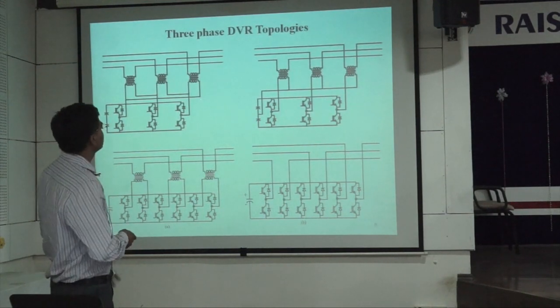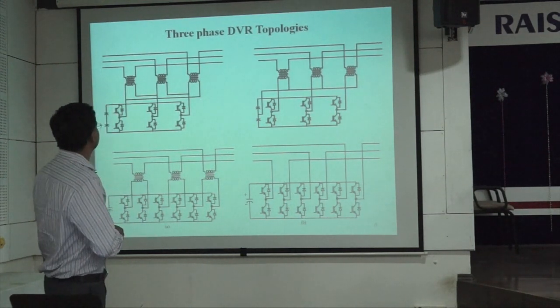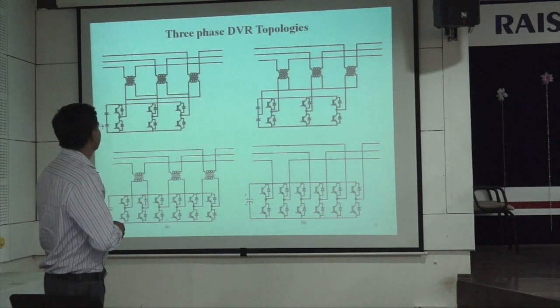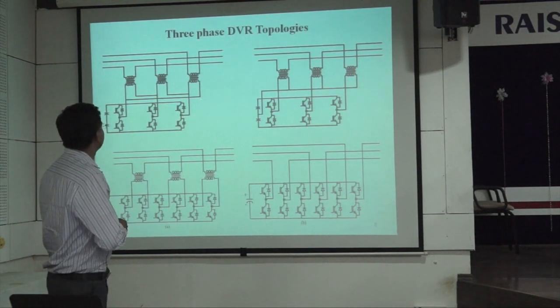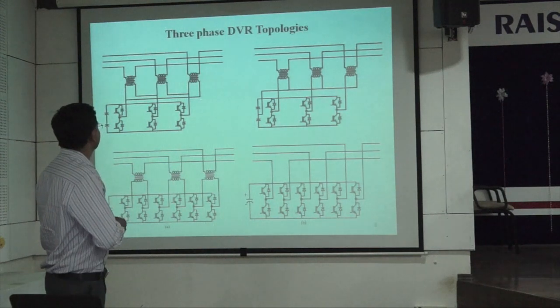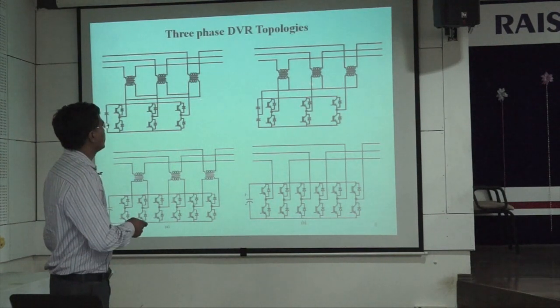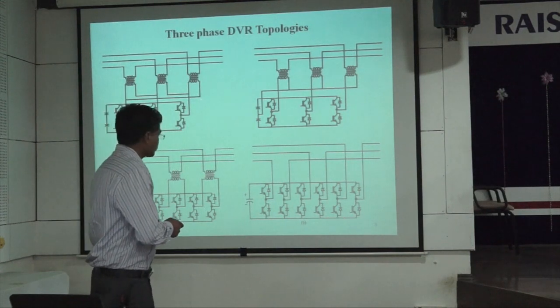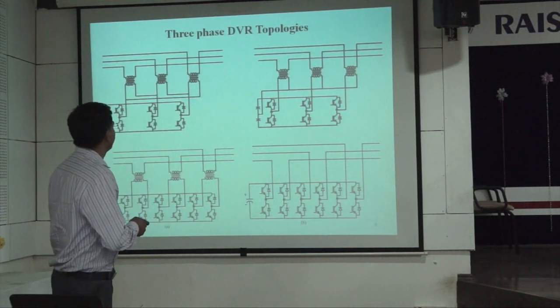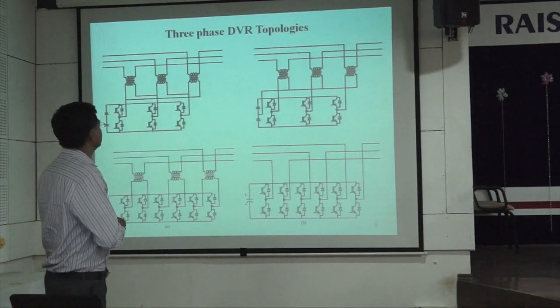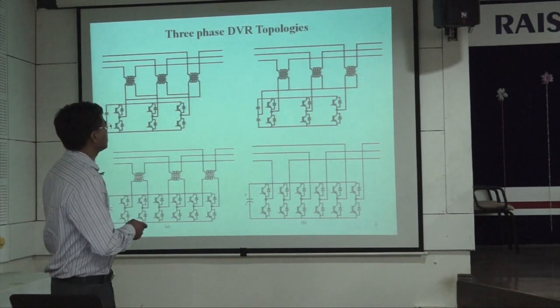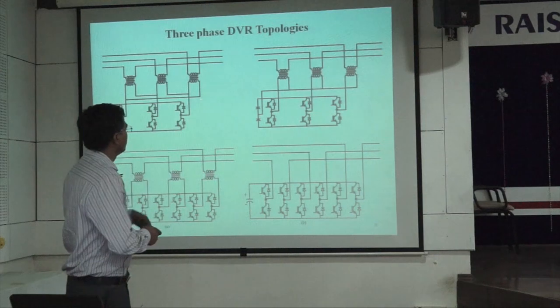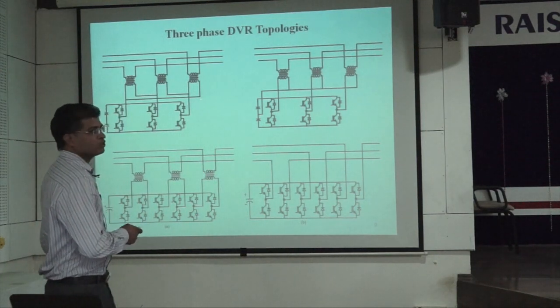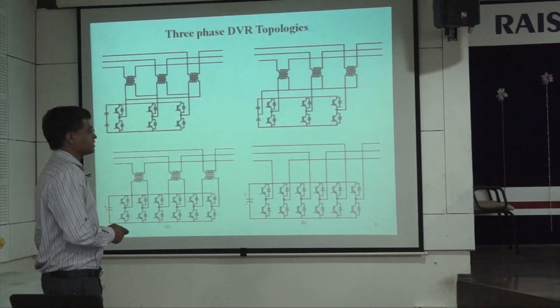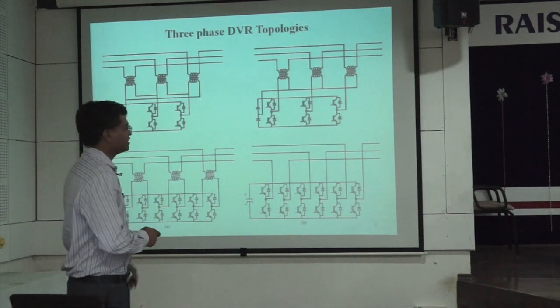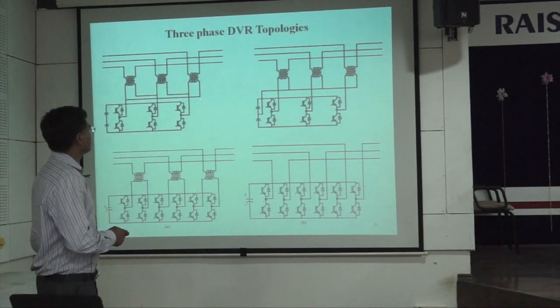Now there are various three-phase DVR topologies. We can connect with the three-arm bridge, that is the H-bridge, with the help of a transformer. These can be connected in delta open fashion, or you can connect in the star open fashion, star open winding. With the delta open arrangement we cannot inject the zero sequence into the system. With the star open arrangement, we can inject the zero sequence into the line. So most of the researchers have now concentrated on the zero sequence component injection into the line. That's why this is the case.